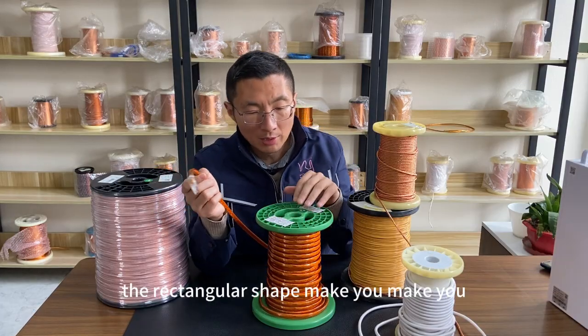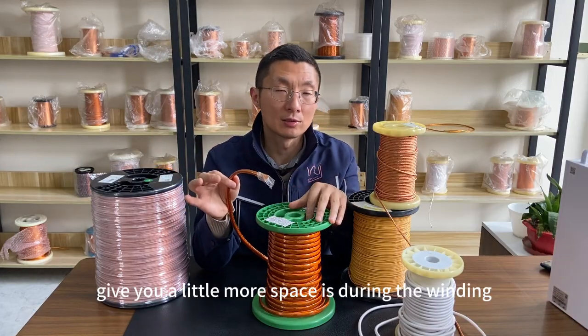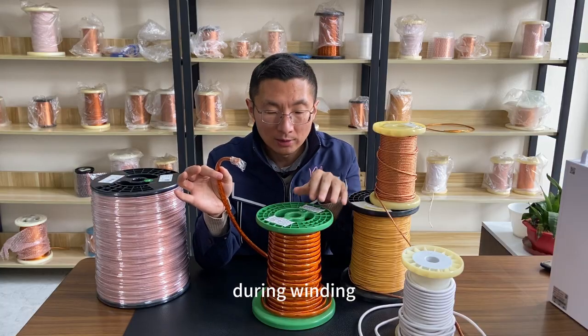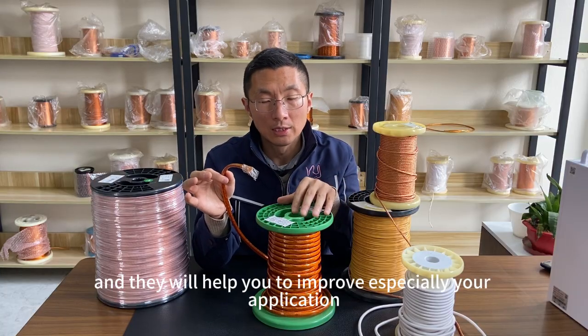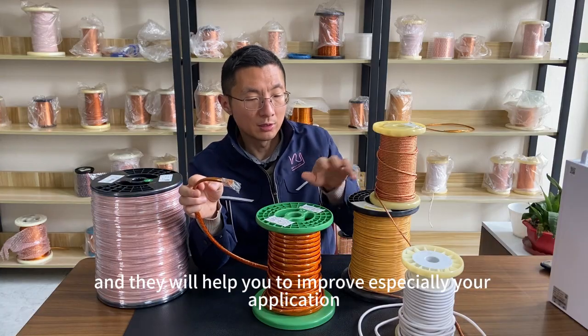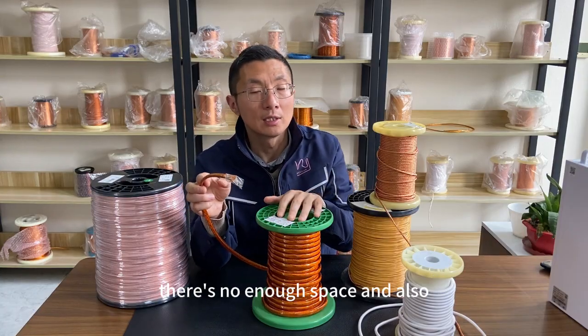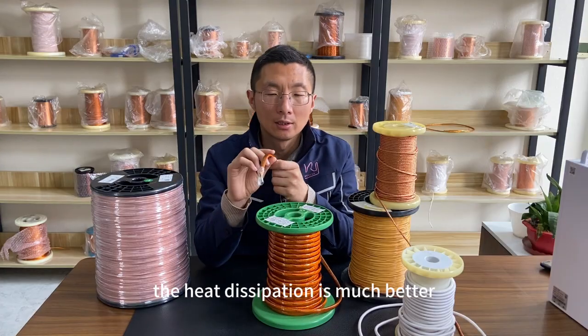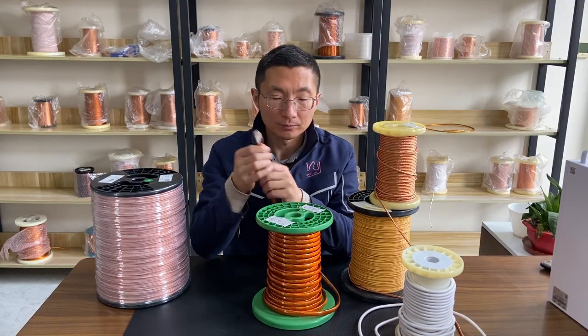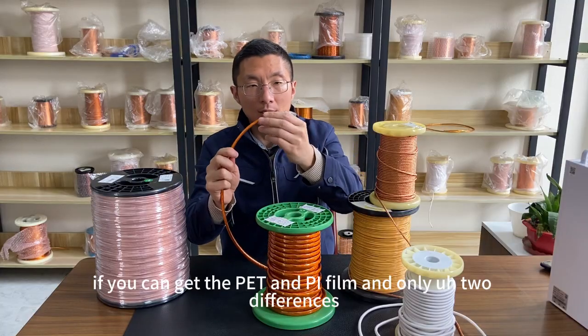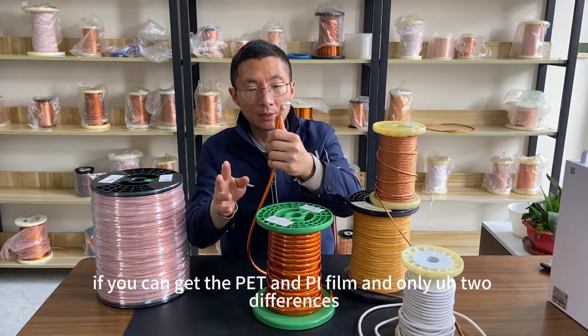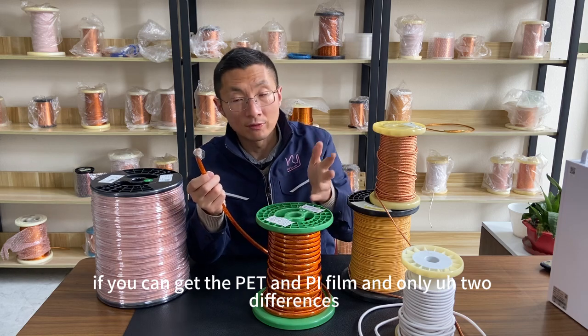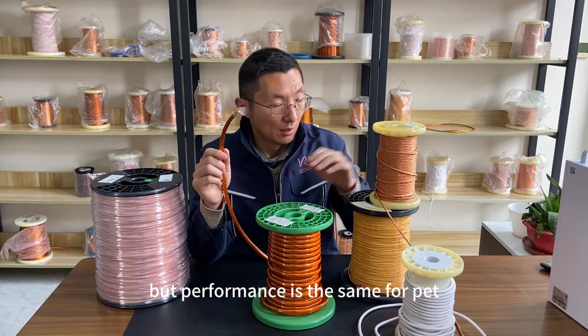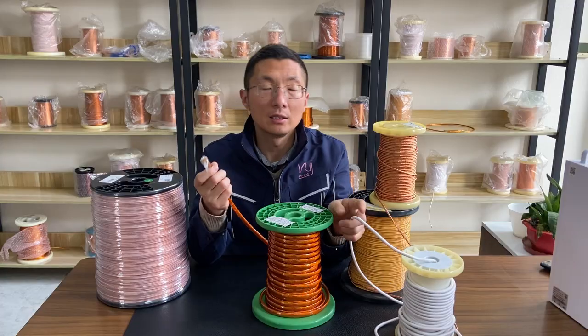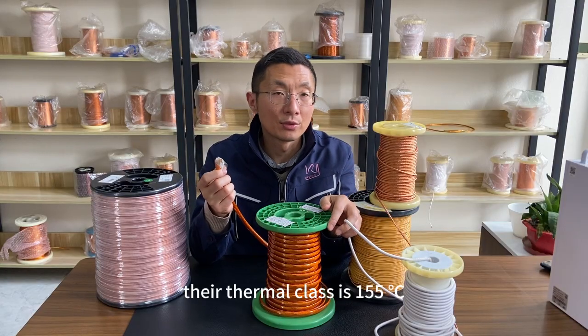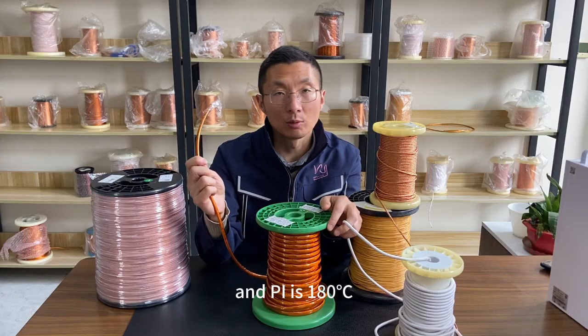The rectangular shape gives you a little more space during the winding, and it will help improve your application where there's not enough space, and the heat dissipation is also much better. With PET and PI film, there are only two differences, but performance is the same. For PET, the thermal rating is 130 degrees centigrade, and for PI it is 180 degrees centigrade.